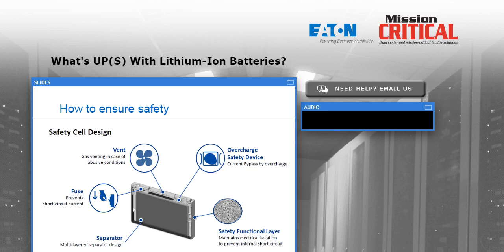And as you may know, the internal gases that would be emitted in that case for valve-regulated lead-acid are actually toxic. So the good news is that lithium batteries do not emit toxic gases. The bad news is they do emit flammable gases. So we want to make sure that this battery doesn't get in a mode where it has to vent. But there is a vent there if necessary so that it doesn't break the case.